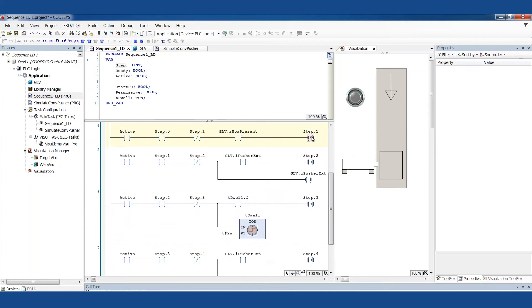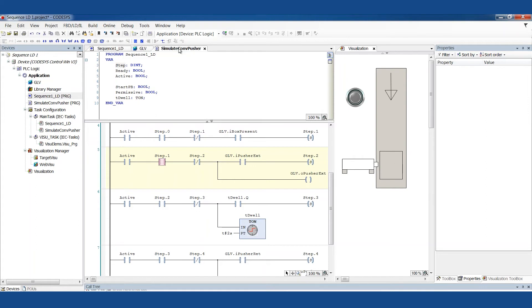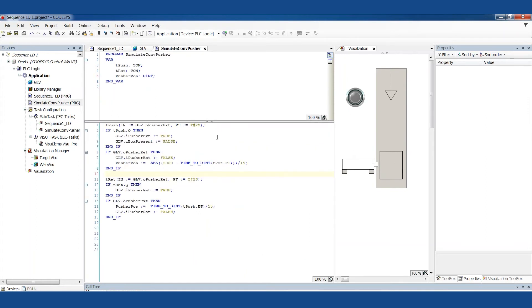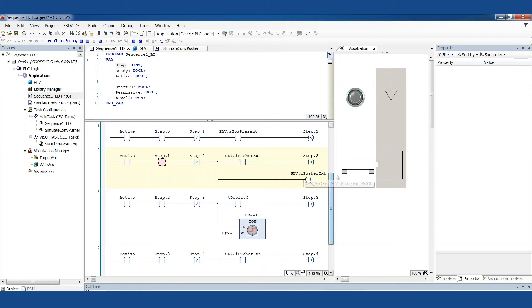After there's a box there, step one happens. We're on this rung now. We're going to start sending this output, the little O for output, pusher extend. So we're going to start extending this pusher. Now, I've created some logic in the background that times that pusher extend and retract and helps this move and stuff. I'll show you briefly what it looks like. I'm not going to go over this right now. I just want you to know it exists. That's what's lighting up these indicators and moving that pusher. So we're just going to pretend that things that start with I here are actual inputs from real sensors and things that start with O are actual outputs to real valves that are firing the cylinder.